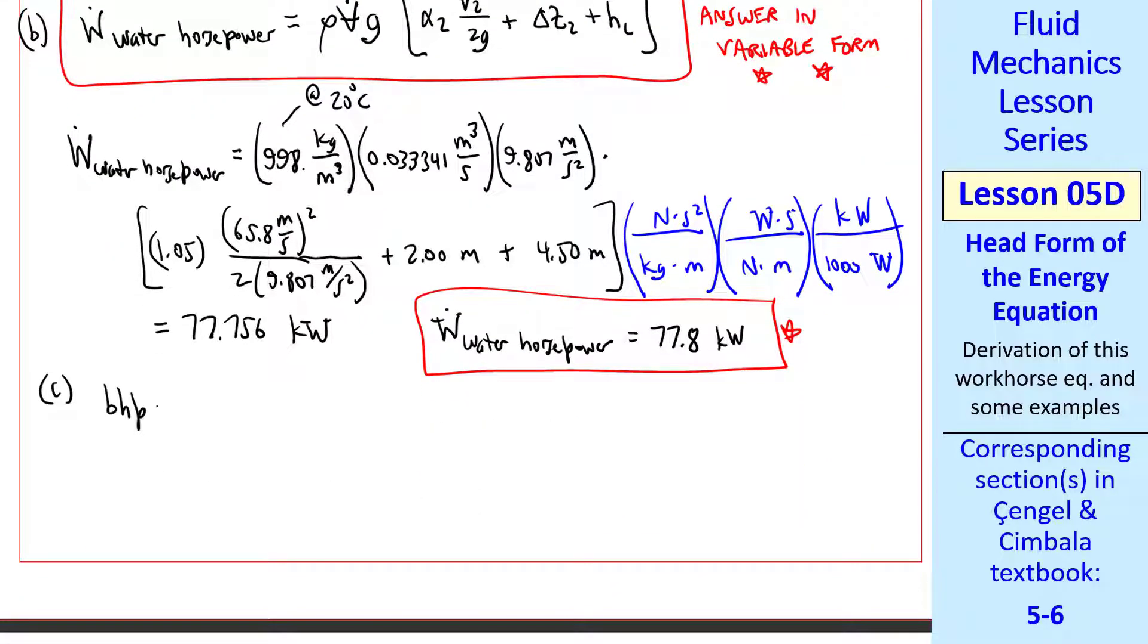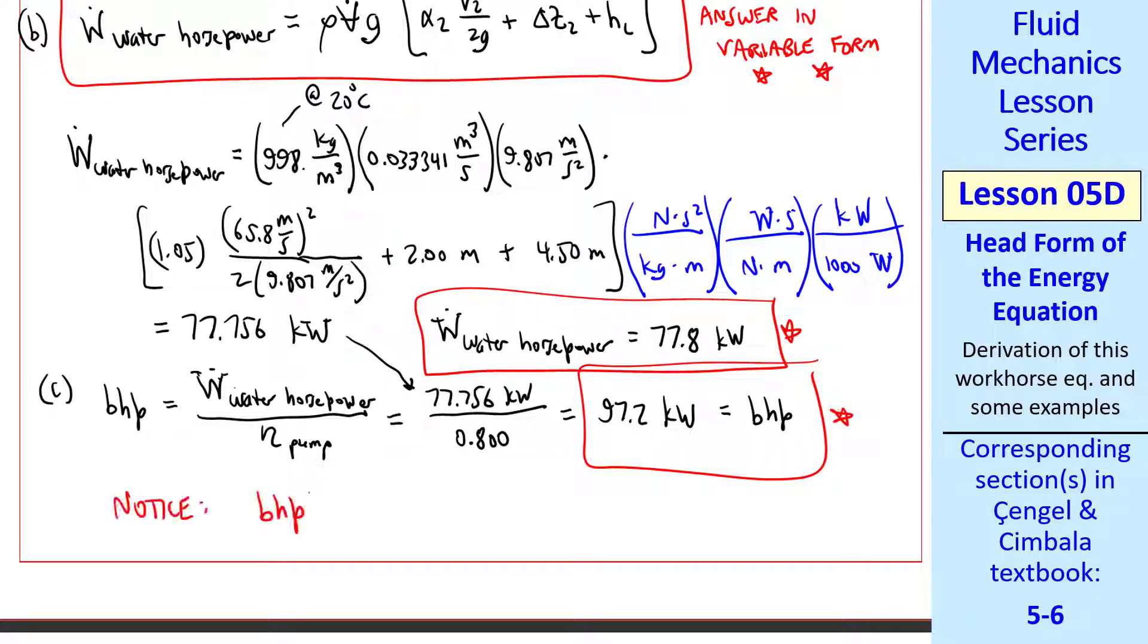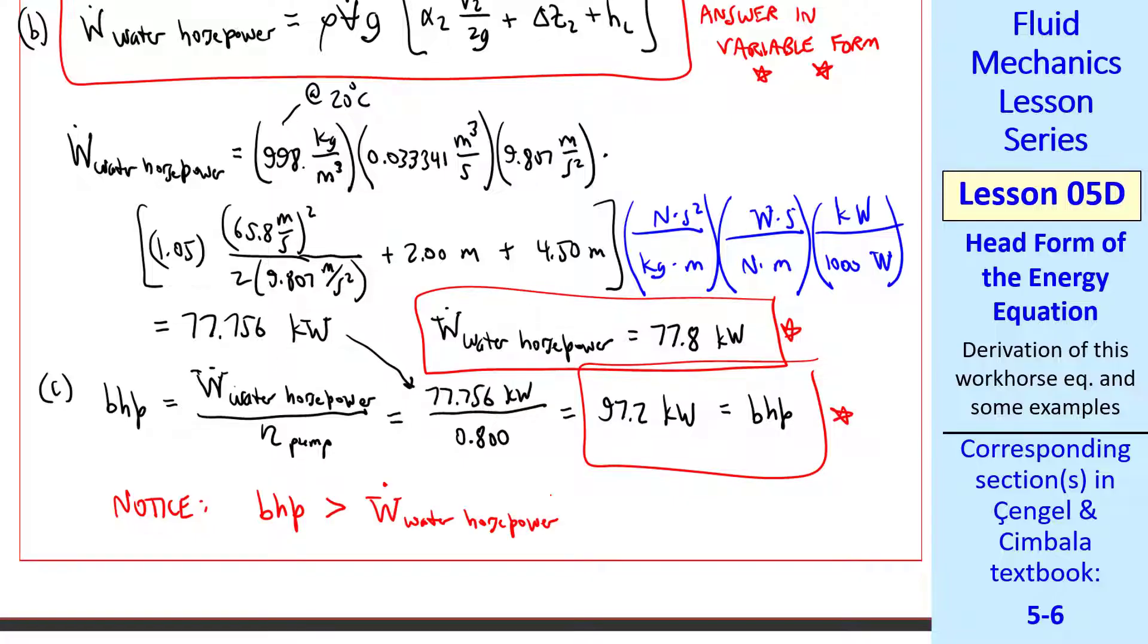Finally part C is to calculate the brake horsepower, which we abbreviate BHP, which by definition of the efficiency is the water horsepower divided by eta pump. So we use our water horsepower and the given efficiency, and we get 97.2 kilowatts as our brake horsepower. Notice that BHP, which is the actual shaft power supplied to the pump, is greater than the power supplied to the water, and that's due to pump inefficiencies.